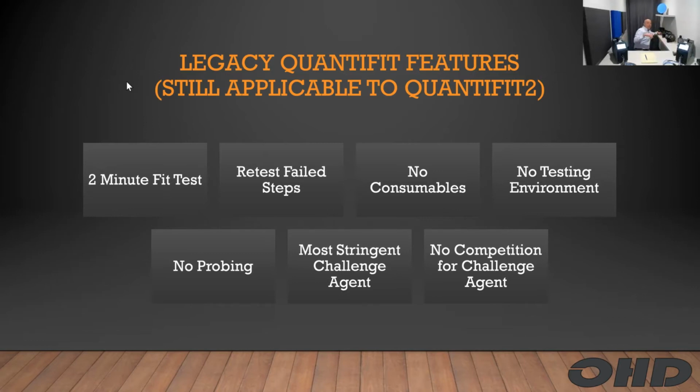We are going to continue to connect to the respirators using the exact same adapters we did with the legacy QuantiFit, and the adapters just connect to the mask the same way a filter does. So you'll never have to probe the respirator. You'll never have to have probing supplies, or worry about cross-contamination concerns with probing supplies. None of that is involved with a QuantiFit2 test.